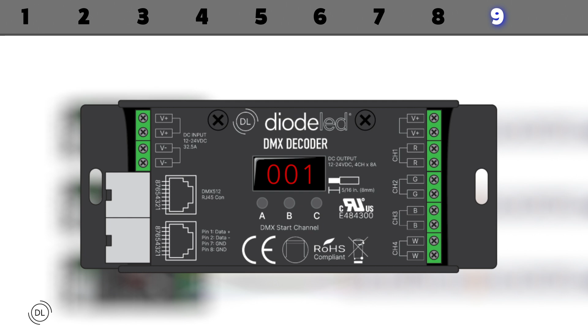To reset the DMX decoder, you hold the first and third buttons together for 3 seconds, where the decoder display and fixture will flash. Once an address is selected for your fixture, the remaining 3 channels will be utilized digitally. For example, if the DMX decoder is addressed to 001 on the display, then channel 1 is assigned to 001, channel 2 is assigned to 002, channel 3 is assigned to 003, and channel 4 is assigned to 004. Once the display stops flashing, the DMX address is set. The indicator light will light red when the data signal is confirmed. You will repeat this step for each DMX decoder, assigning each appropriate address based on the number of channels used.